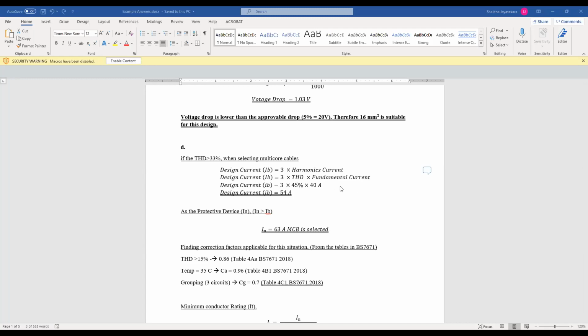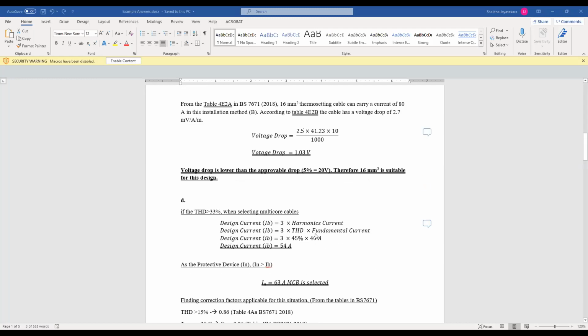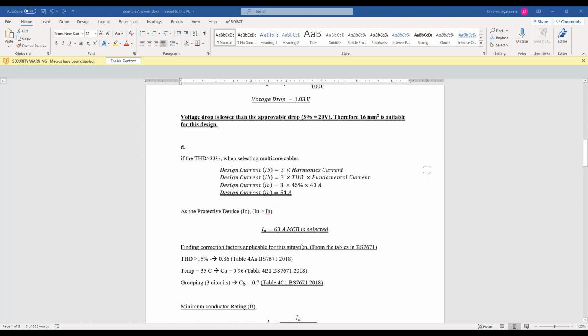So if you design your multi-core cable based on your line current, that means let's say you have only considered 40 ampere line current. But in a case like this, your three phases will be supplying 40 amperes, but in your neutral there will be 54 amperes. So neutral will heat up and it will get burned. So usually it can create a fire. So that's why we are going to do our design like this, based on the neutral current.